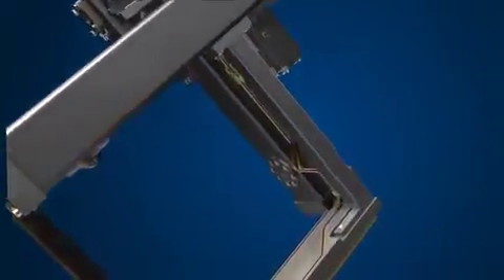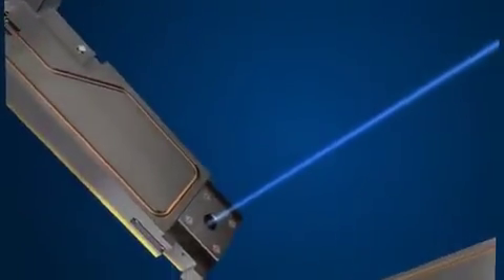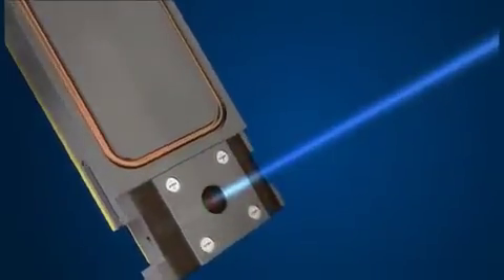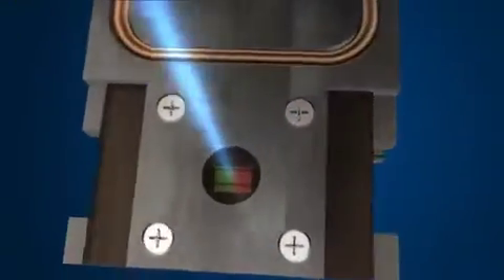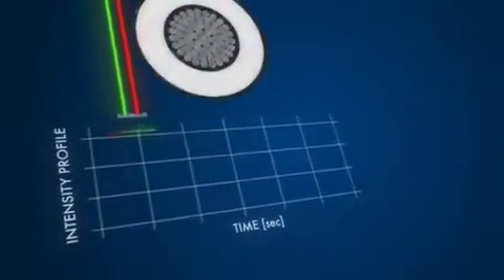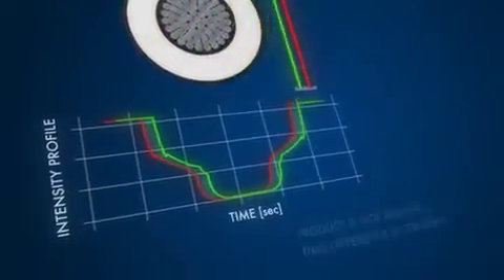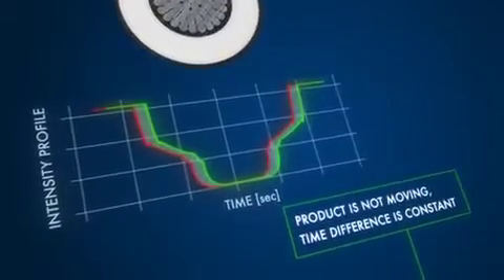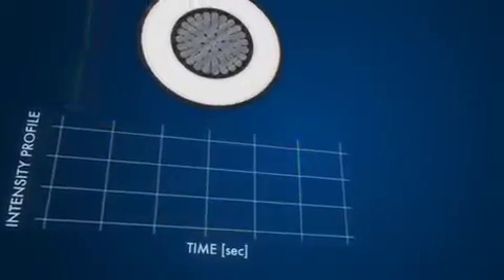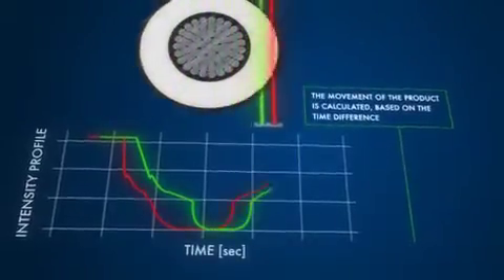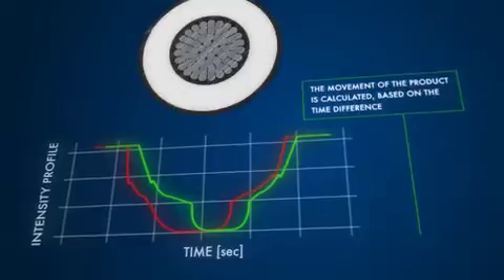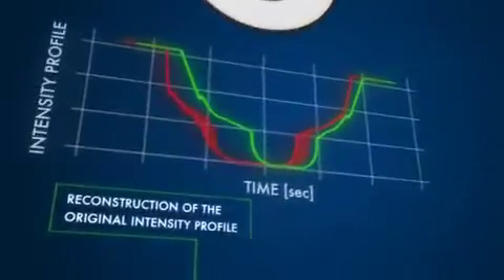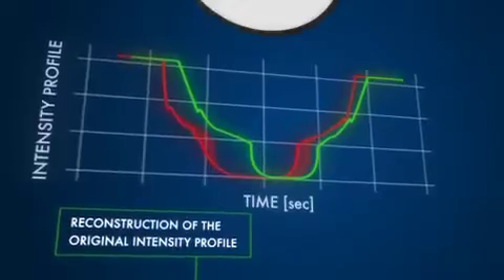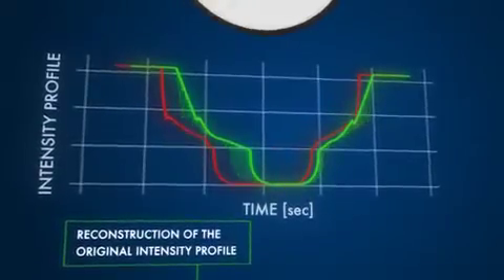The X-ray 8000 NXT is equipped with multi-sensor semiconductor detectors. The multi-sensor technology guarantees, in combination with the high-speed scanner, a reliable and precise measurement of medium, high, and extra-high voltage cables, even when the cable is vibrating. If the cable isn't moving, the time difference between the two scan curves is constant. Production-related vibrations of the cable are represented by a time difference between the two scan curves. With the multi-sensor technology, vibrations of the cable are detected and compensated. Precise measuring values are continuously achieved.